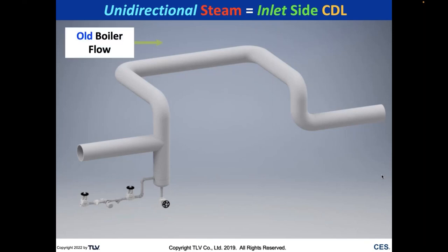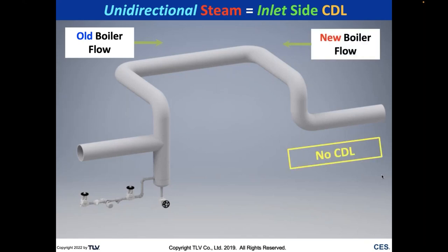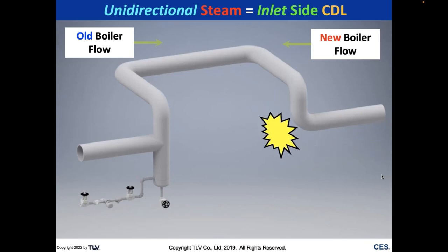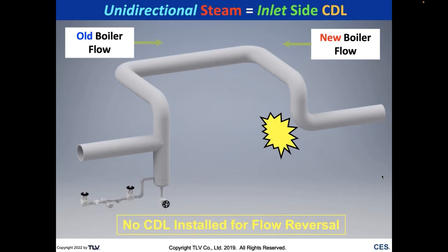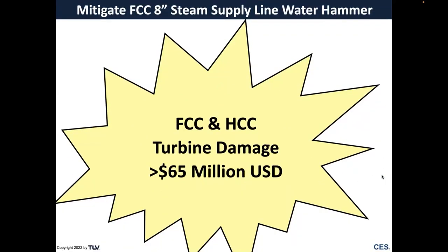Another problem: one refinery's old boiler flowed in one direction with a CDL in place, but when they switched to a new boiler they didn't add a CDL for the new flow direction, damaging those elbows. When you have flow reversal, make sure vertical risers have traps at the bottom to discharge condensate. That was the cause of the FCC and HCC turbine damage in the United States — estimated at 100 to 160 million dollars.